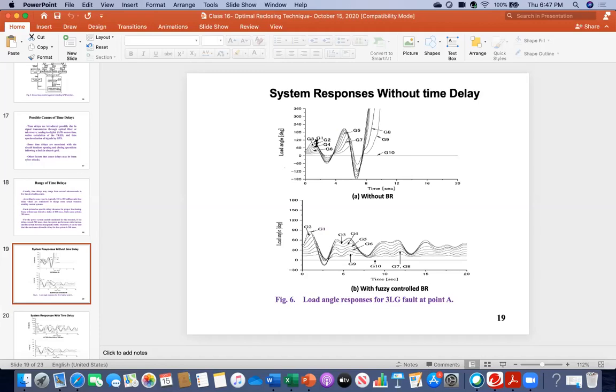That's overshoot. Came back. Keep in mind, the governor is working properly, the circuit breaker, everything is working, but still it did not help. It looks like then it jumped up. And because there is a huge hiccup, huge overshoot, to compensate, it came down. Then it went up and it never came back, and it is gradually increasing. So by looking at this, that is the reason, you see, I simulated this up to 20 seconds.